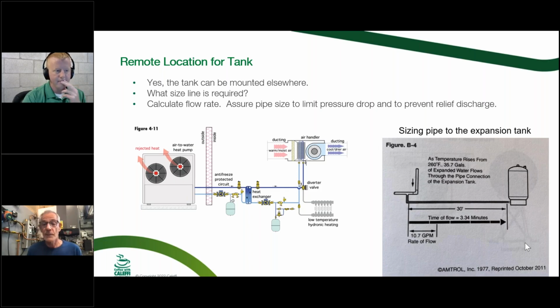And the other one, since we're right here: somebody said, if I do have 30 feet of pipe, and I fill up my system, let's say we've got a diaphragm type, do I have to purge the air out of that line? I asked Siggy and one of the Amtrol people whether there is a problem if that air is in there, and we're of the opinion that eventually that air is going to get absorbed and come out of your air purger if it's trapped in that 30 feet of pipe. If you want, you could loosen the expansion tank and bleed it out as you're filling, or put a Webstone valve on there that has a little purge cock that you can purge from either direction, to purge the little air that's trapped in that 30 feet of pipe. But unless somebody else has a reason, I don't know that air trapped as you fill that would be a bad thing or would affect anything.